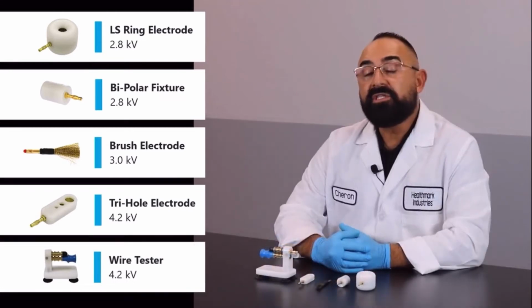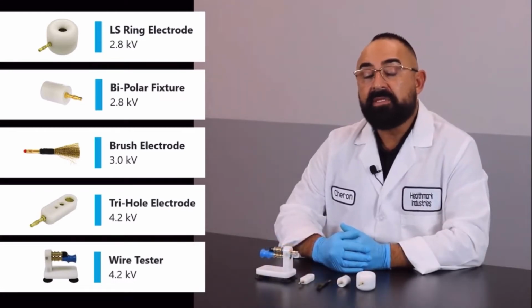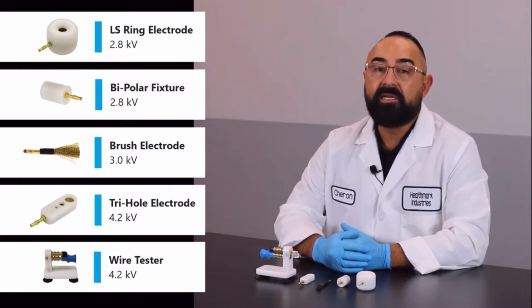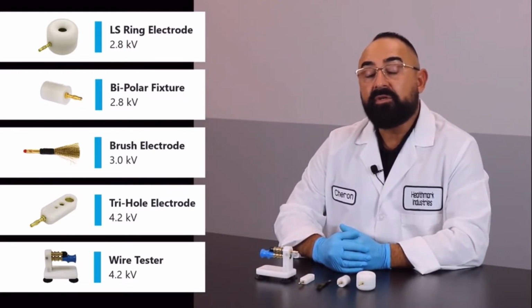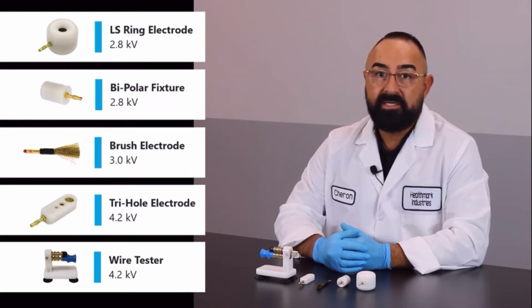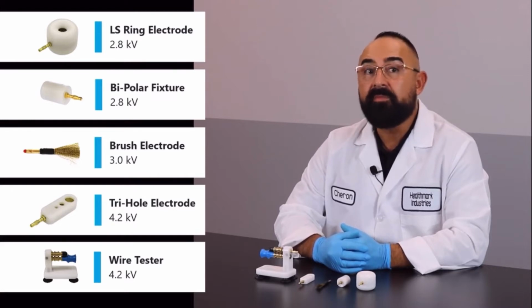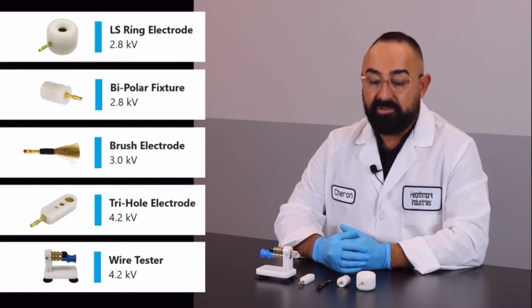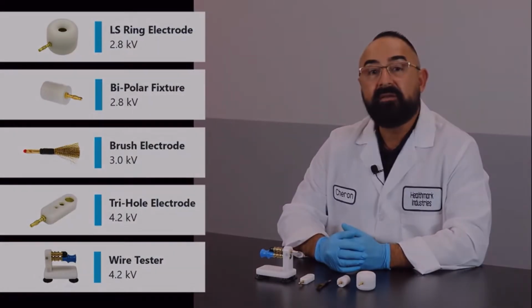If the voltage is too low, then you may not be able to detect the damage in that type of insulation on an instrument. If the voltage is too high, you could damage the insulation as well, and this is why it's so important to make sure that you're setting the voltage to exactly what the accessory that you're using.